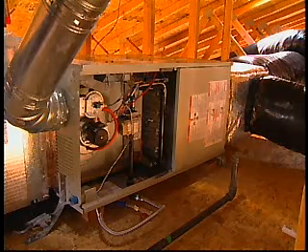Sheet metal joints leaking, where flex ducts connect to sheet metal, and all the attachments at the equipment itself are typically the largest leakage culprits. And what about supports? Oh yeah, all the time — installers sometimes miss supports.